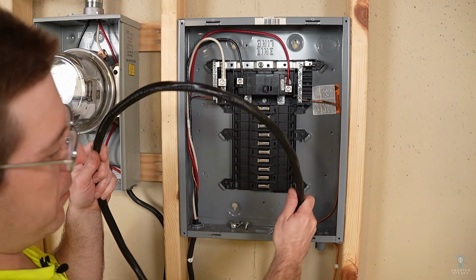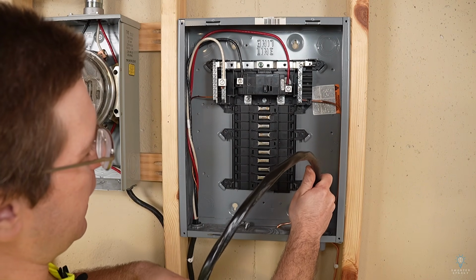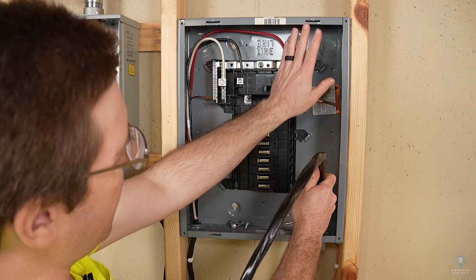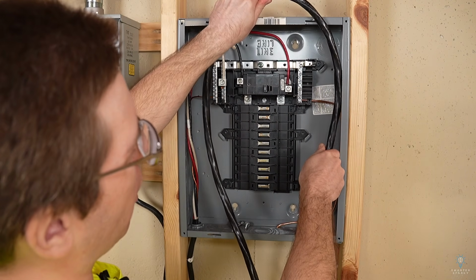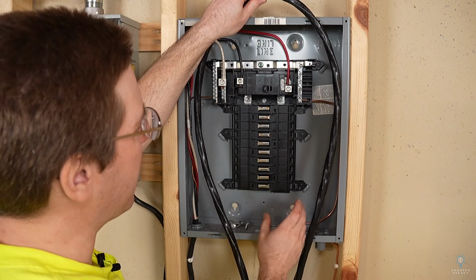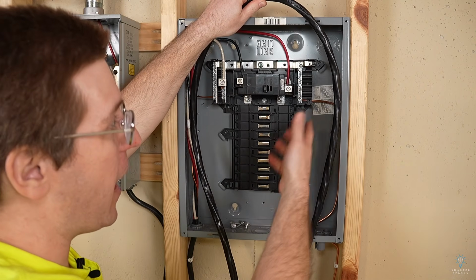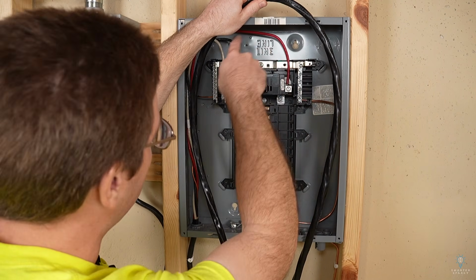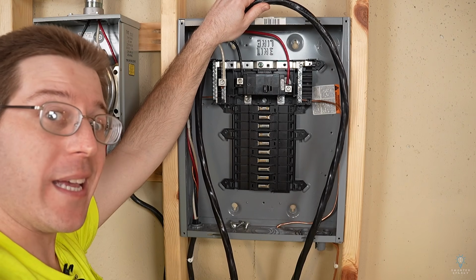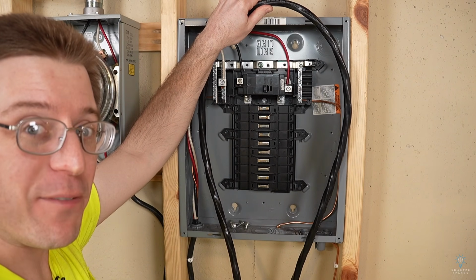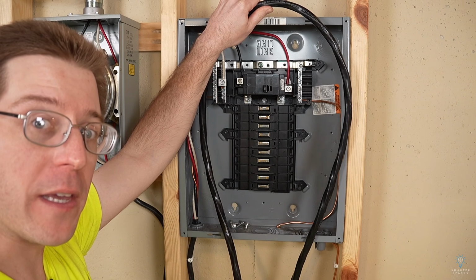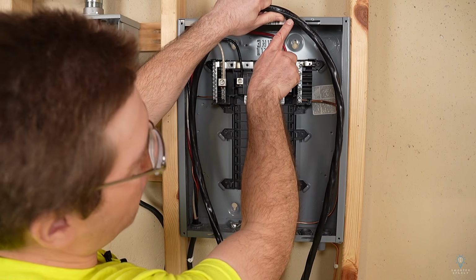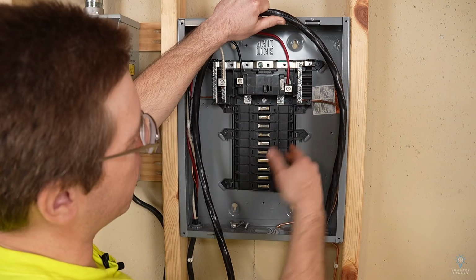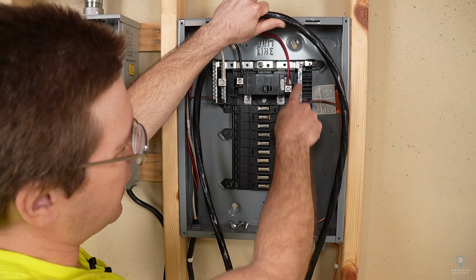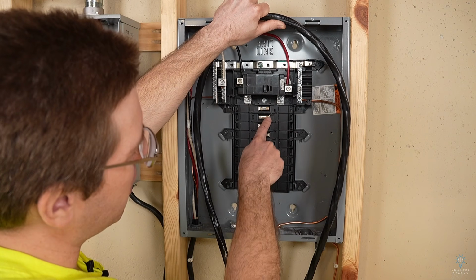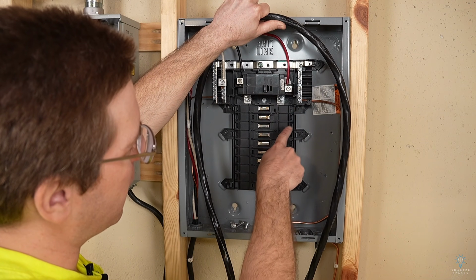So we'll estimate how much wire we need. I am going to be landing all of my stuff on this side of the panel. So really I just need wire long enough to get to the top of the panel in my case right here. Again, it's better to have more than enough, so it's better to always just loop up and over. Yes, you waste a foot of wire, but that might save you from wasting that full 100-foot run that you just ran. So I'm gonna cut my wire approximately right here. That way I've got a little bit of room. Basically our grounds and neutrals are gonna land right here, and our two hots, I'm gonna install the circuit breaker in this area right here.